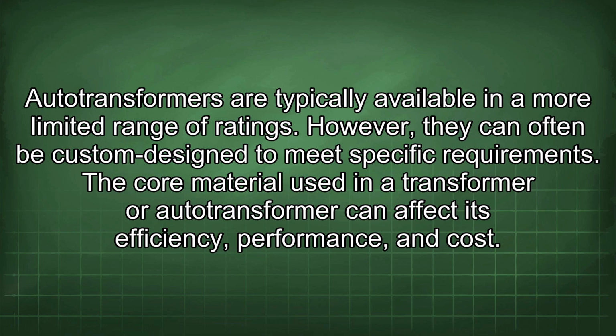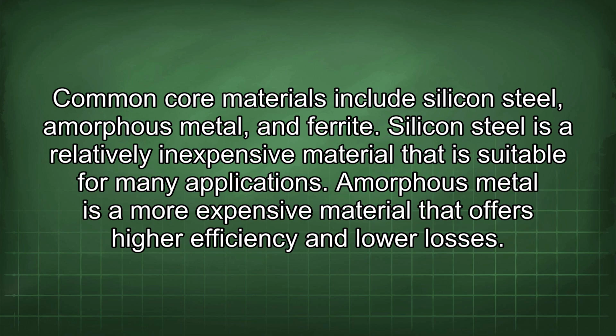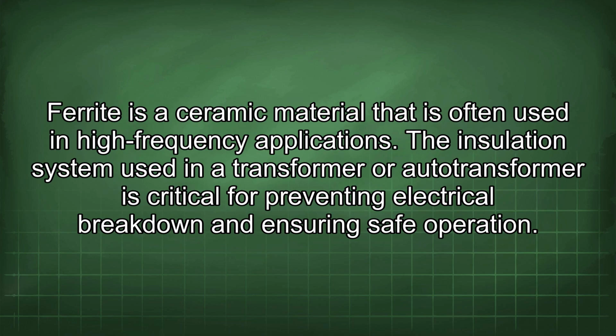The core material used in a transformer or autotransformer can affect its efficiency, performance, and cost. Common core materials include silicon steel, amorphous metal, and ferrite. Silicon steel is a relatively inexpensive material that is suitable for many applications. Amorphous metal is a more expensive material that offers higher efficiency and lower losses. Ferrite is a ceramic material that is often used in high-frequency applications.